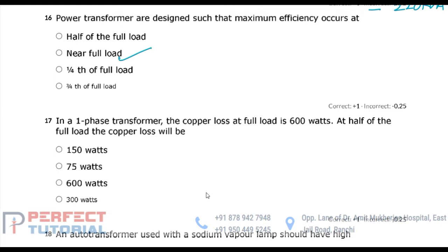Next question is: in a single phase transformer, copper loss at full load is 600 watt. At half of the full load the copper loss will be? The copper loss at full load is known, and we have to find it at half of the full load. You have seen a similar question before. At half load, copper loss would be half square into the full load copper loss, that is equal to 1 by 4 times 600 watt, that is equal to 150 watt.